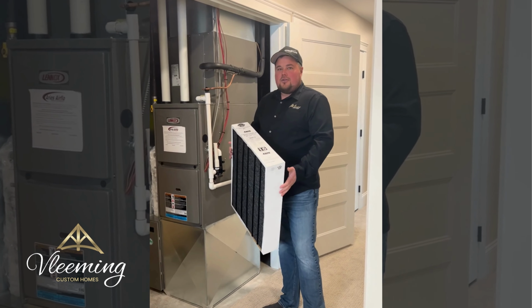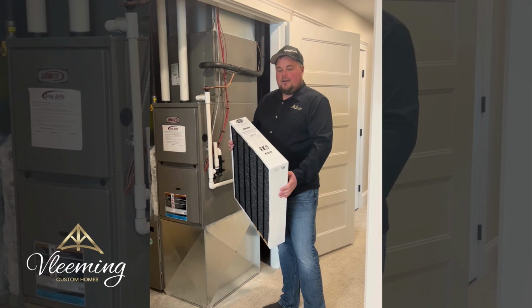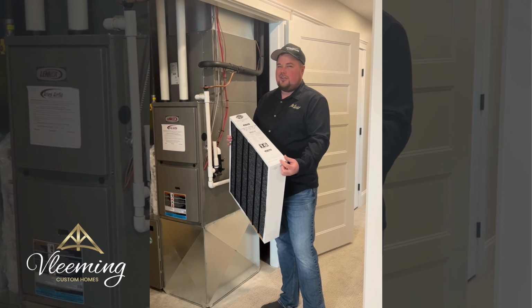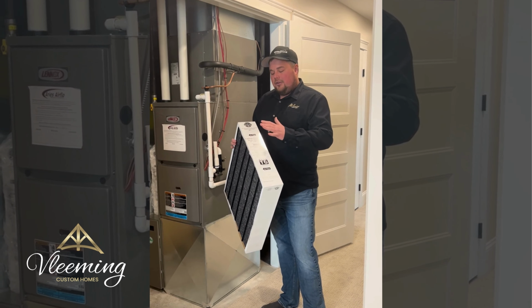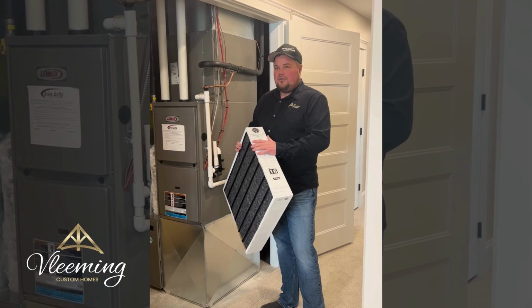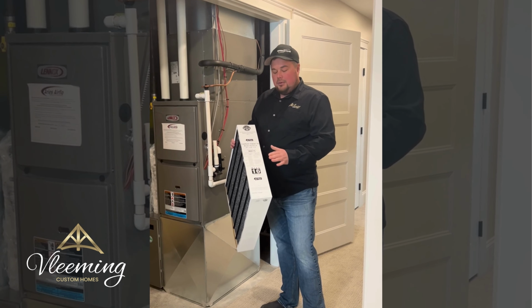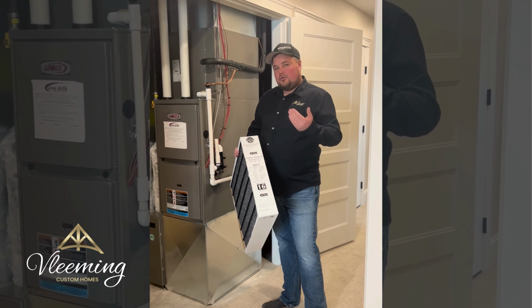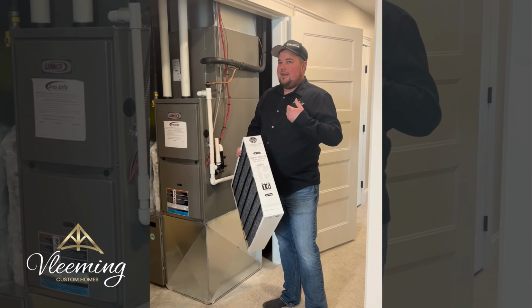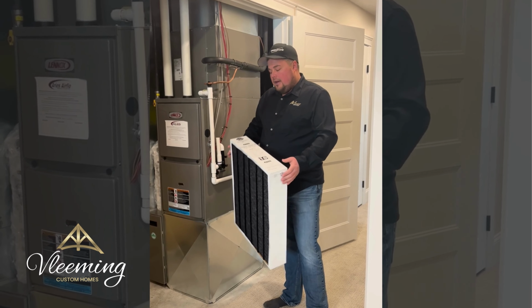Part of the furnace is filtration. You need to make sure that you're having a good filter on it. Just a simple little 1-inch filter doesn't do a lot. So every house we have, we allow for a 5-inch filter housing. That allows you to put in a bigger filter to get better air filtration to keep your house cleaner and keep the air you're breathing cleaner.